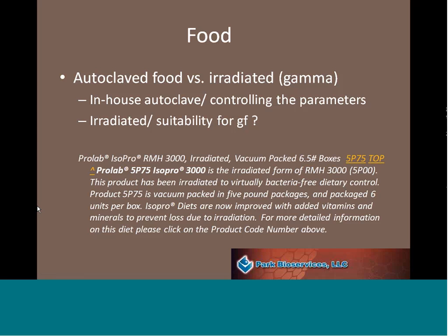Well, what can happen is that you can go to irradiators if you have a sufficient lot of things to be irradiated and have the additional dose added. And if anybody is interested in pursuing that, I could give you some guidelines as far as the additional radiation. But it's important to note that irradiation is cumulative, so if it's irradiated at so many megarads, and what you need for total sterility is X, you just have to add the additional irradiation.